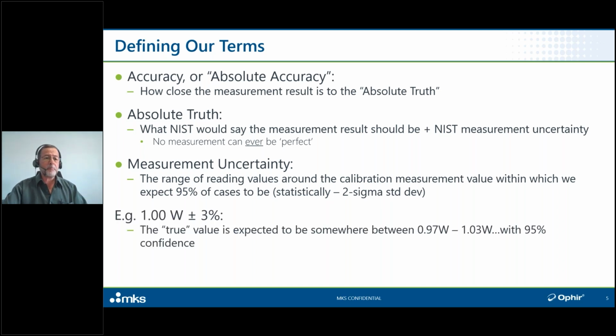So just for example, let's say you use a laser power measurement, a power meter from Ophir, and you're measuring 1.00 watts. And the data sheet of that particular instrument tells you that its measurement accuracy is plus minus 3%. That's a pretty typical value. So that means that the true power of that beam is going to be somewhere between 3% above or below 1 watt. And even that statement, we're saying with a 95% confidence level in the case of Ophir.